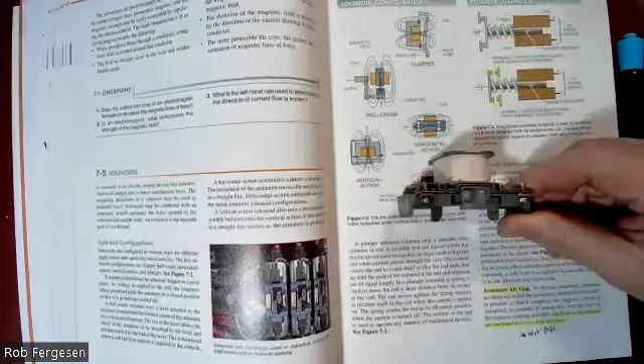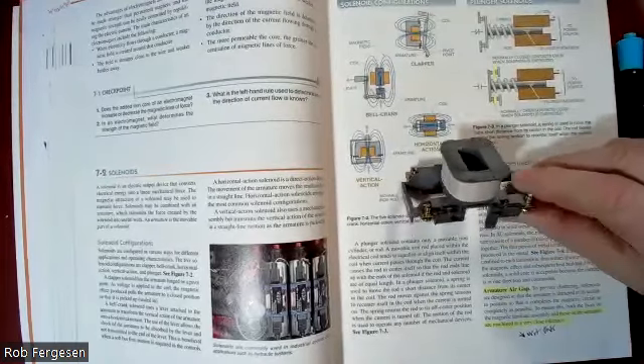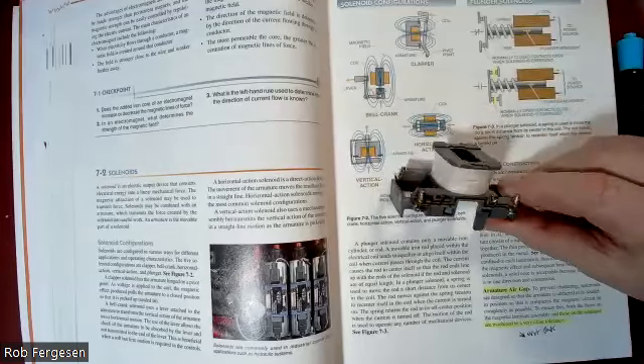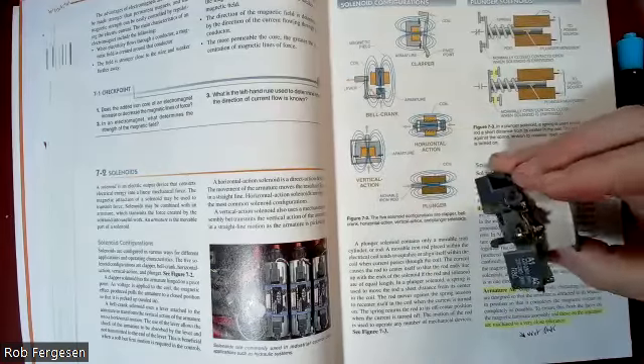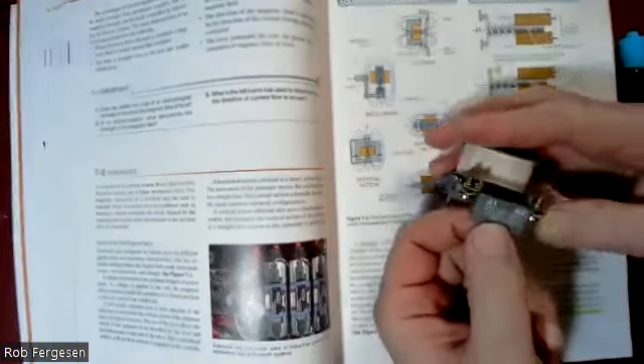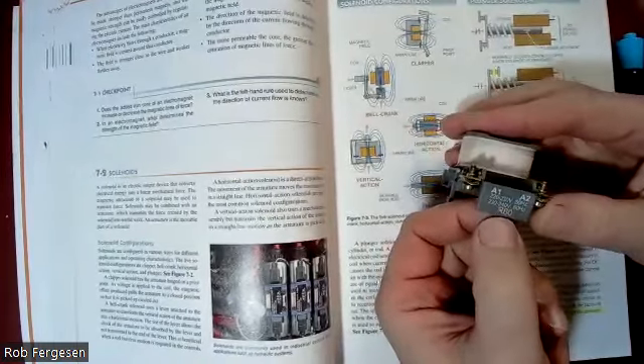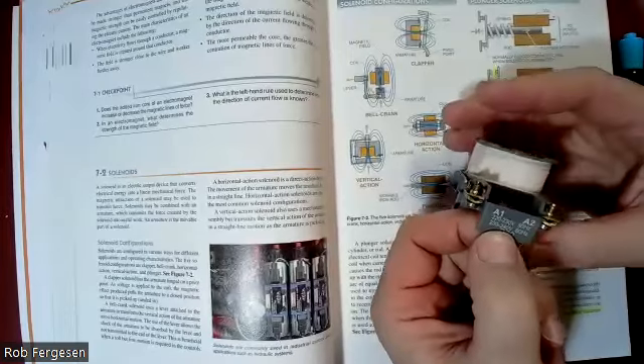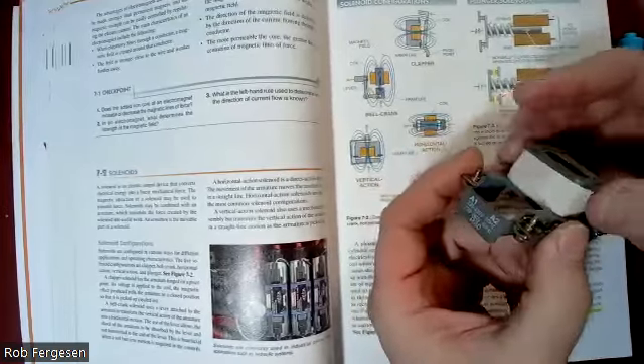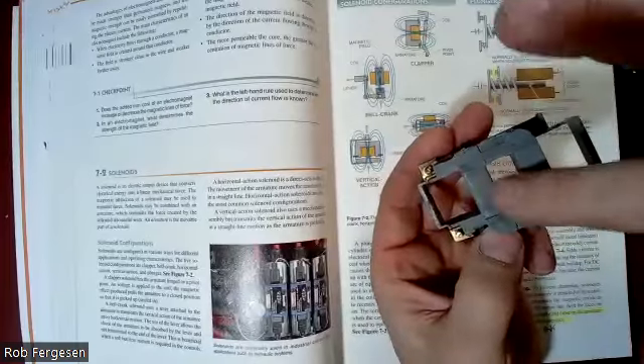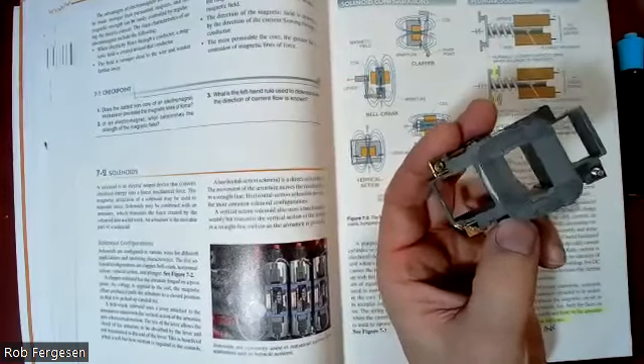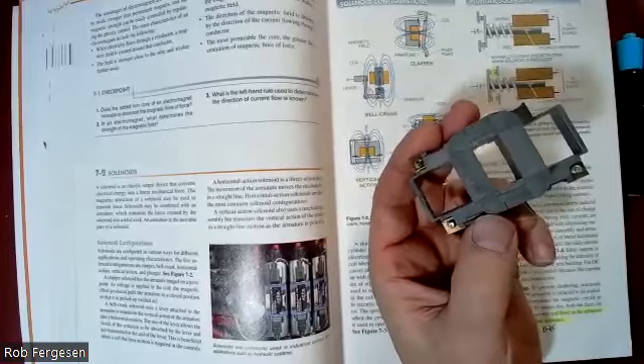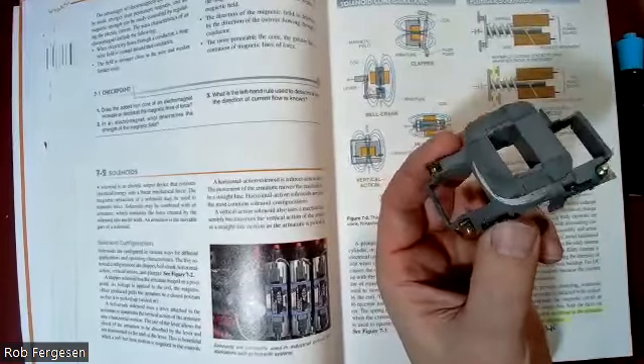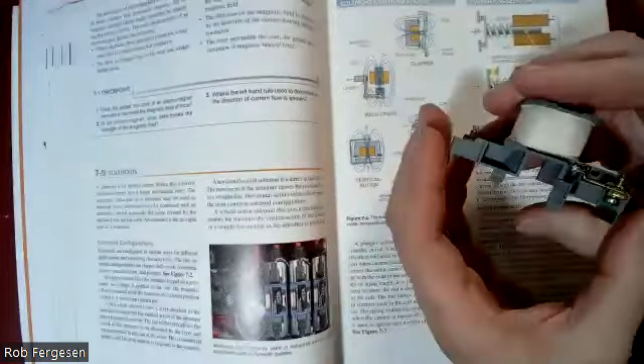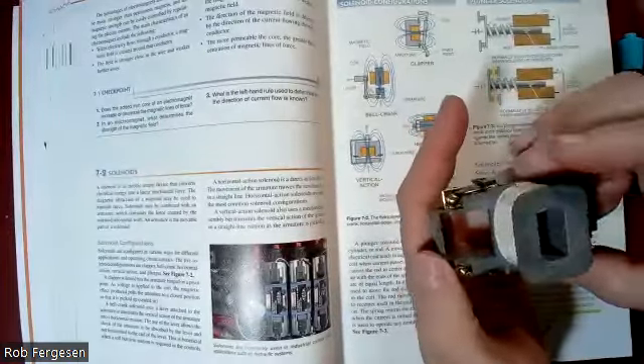So replaceable coils, in the case this is an ABB contactor coil, is critical. And so recognizing the coil, how you can remove it, how to specify that coil, how many volts is it? Very, very important. What kind of voltage does it take? You need to match it exactly in terms of configuration, size, the little hole, the steel parts of your magnetic configuration need to match exactly. So buying this coil can sometimes be a very tricky process. So you've got to do that right.